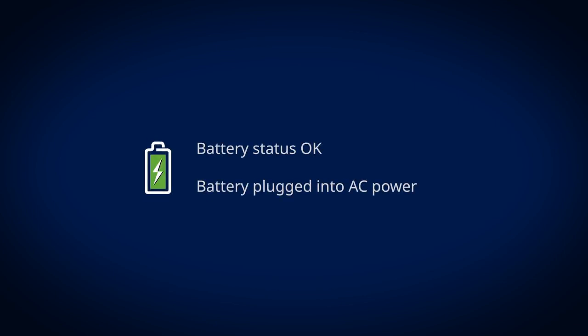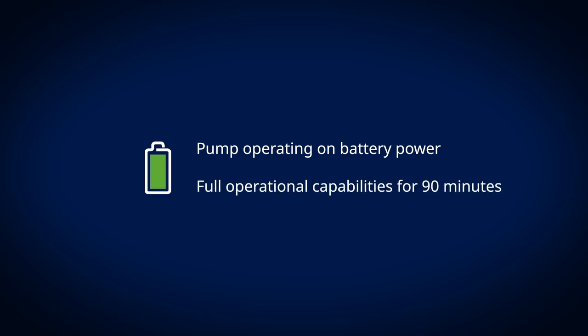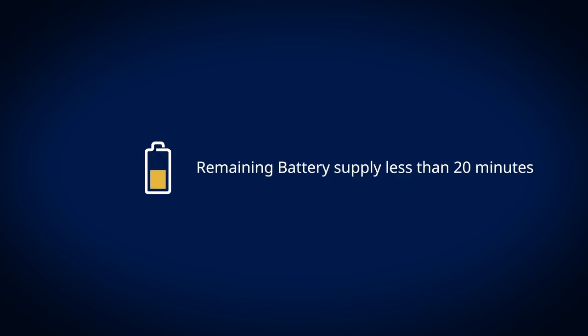A green battery icon with a lightning bolt indicates the battery status is okay and plugged into AC power and charging the battery. A solid green battery icon indicates the pump is operating on battery power. The battery system allows you to use the system with full operational capabilities for a minimum of 90 minutes. A yellow battery icon indicates the battery status is okay, but the battery charge is estimated at less than 20 minutes. This will also be associated with a battery less than 20 minutes alarm.